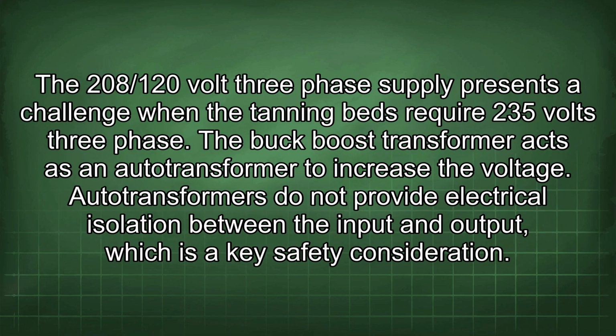The 208/120 volt three-phase supply presents a challenge when the tanning beds require 235 volts three-phase. The buck boost transformer acts as an autotransformer to increase the voltage. Autotransformers do not provide electrical isolation between the input and output, which is a key safety consideration.